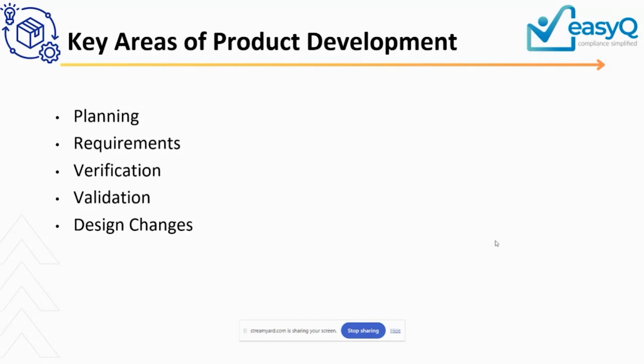And that maintenance activity is linked with your design changes. As Fareen, you rightly mentioned, your products are not going to be the same. The approval that you get versus what will be in the market in the next 3 years will definitely be different, due to many reasons. And at that point in time, if you're not having good controls, if your design change activity is not in line with the regulatory requirements, you are going to be in non-compliance. And when you are in non-compliance, you will see your recalls, you will see your 483s, you will see your non-compliances, and many other things, depending on what the issue is. So, please do not ignore the fact that design change is a very important activity, and you need to consider the applicable regulatory requirements for that, which we'll be talking more about as we move forward.